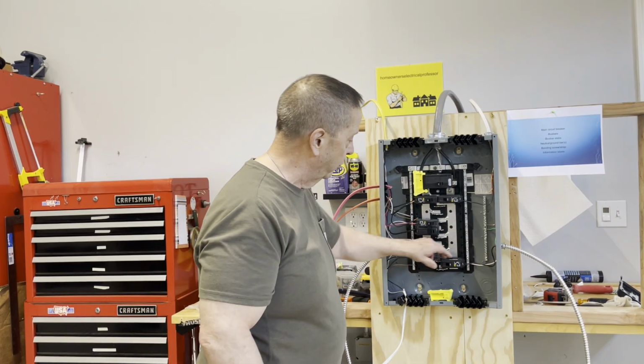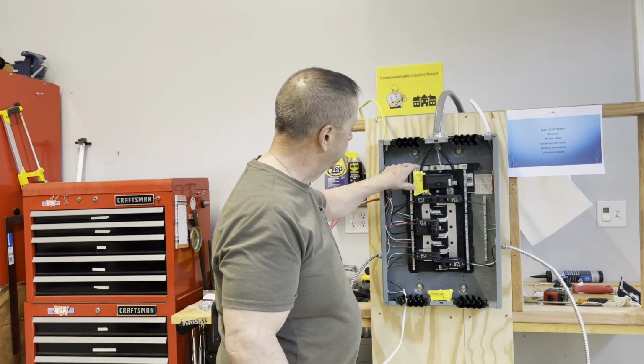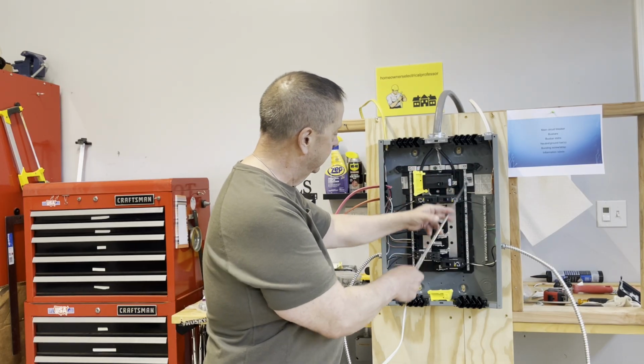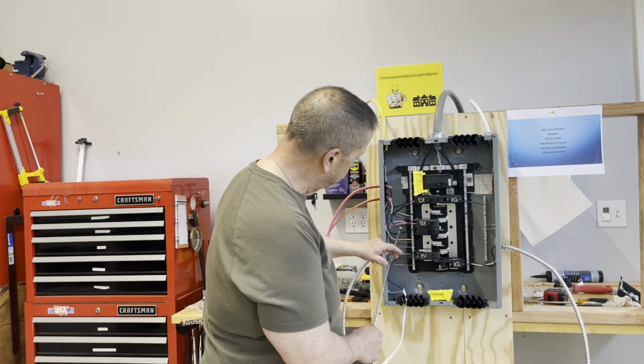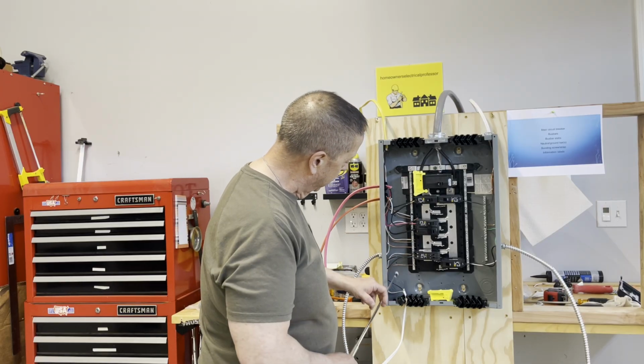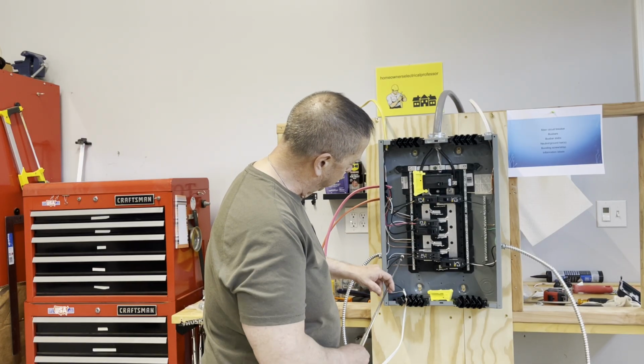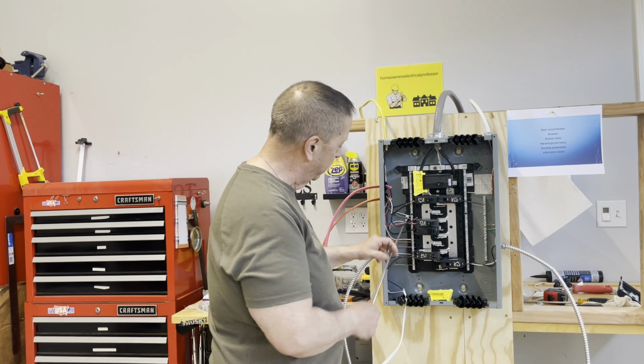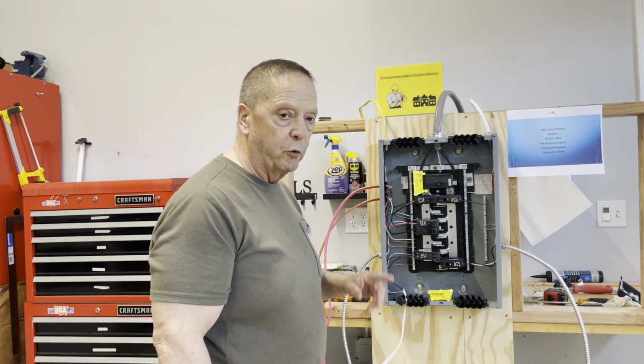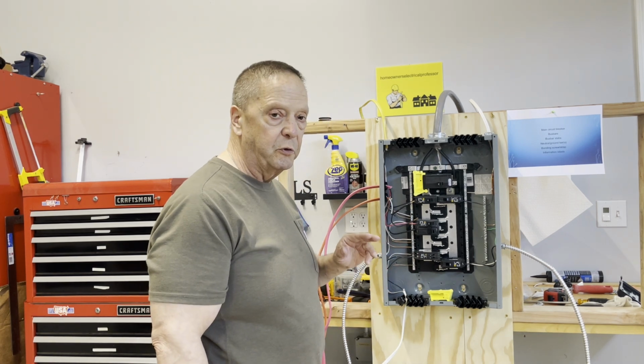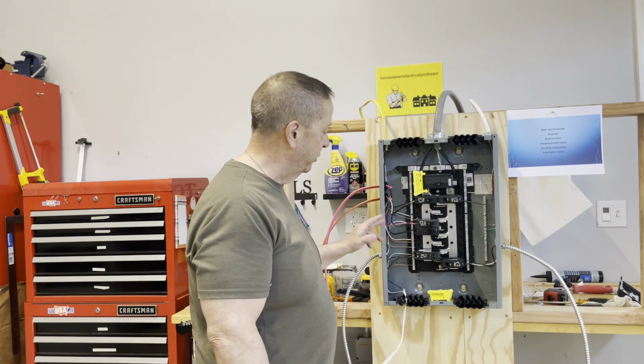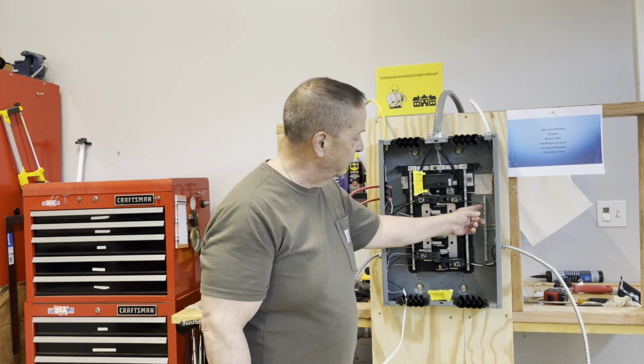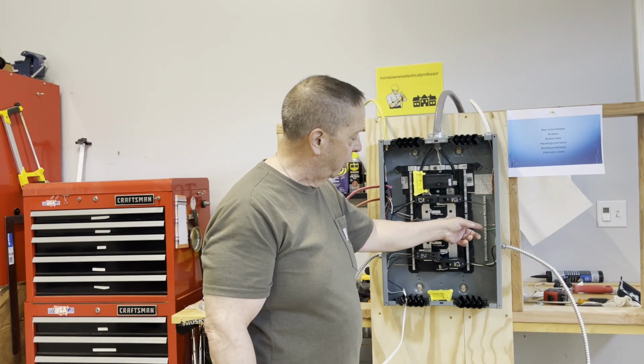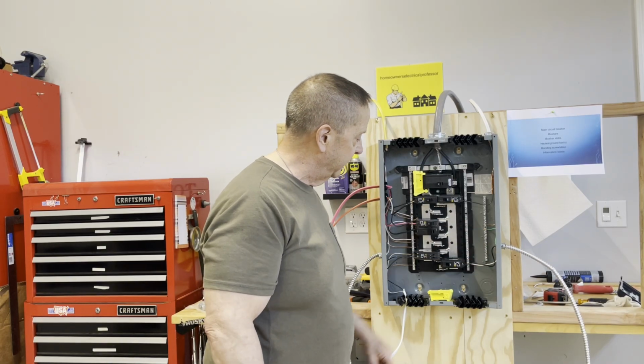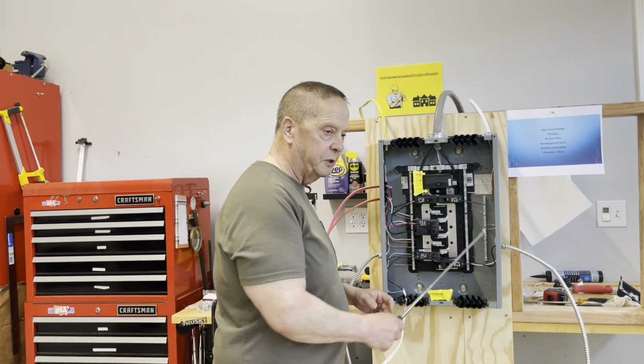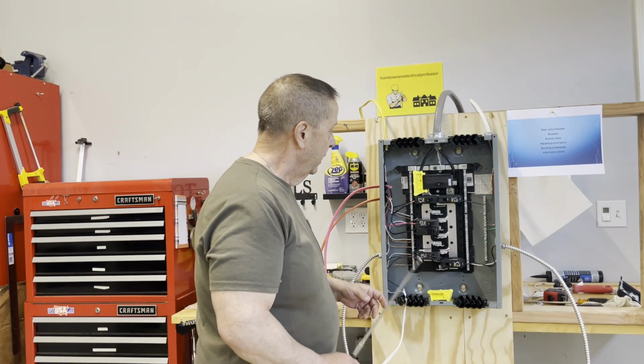And as I told you before, neutrals have to be terminated on the two neutral bars here, which you can see I did down here, but I also terminated the ground wires here, which you can do. Each neutral gets its own screw. You can do two ground wires under one screw, but I also installed an accessory ground bar over here, and I terminated some of that. You may have this, you may not have that.